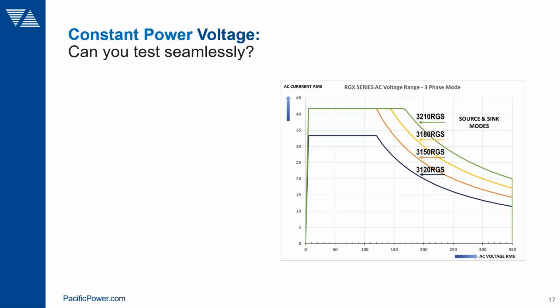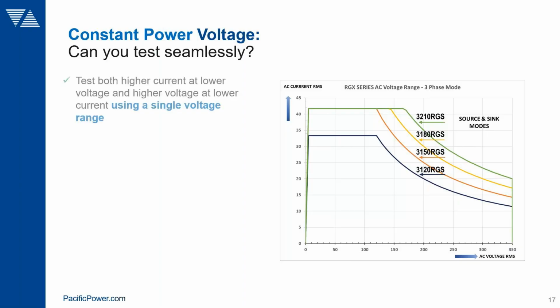Another aspect that you want to look at is, does it have fixed power voltage ranges, or does it have constant power voltage ranges? Constant power ranges, as you see here, combine both high voltage and lower current with lower voltage and higher current capability on the same voltage range. That means you can test a product that has a wide input voltage capability from the low voltage level to the high voltage level without having to switch voltage ranges, as you would with a dual range grid simulator. That means you don't have to interrupt the test and switch the unit off temporarily as you switch between different voltage ranges. Usually dual range systems will have to reconfigure when you switch range, and that means they momentarily have to drop the output.